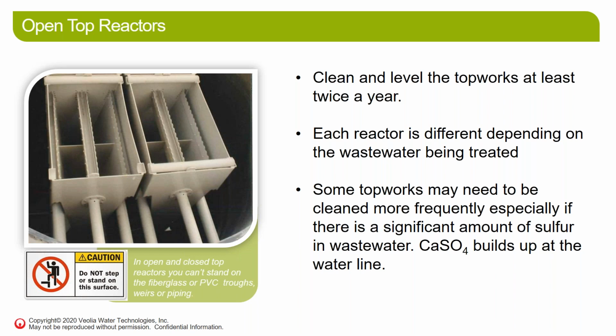So, yeah, in spots where we have more sulfur in the wastewater, calcium, you can get buildup of solids up at the top because in an open top reactor, you have anaerobic effluent with air. So you start producing some solids that kind of plate out or build up in that space where there's air and anaerobic effluent. So a lot of times if you have high sulfate concentrations in your wastewater, that converts to H2S, and if you take your covers off, you'll see this kind of white and yellowish crust and solids building up underneath your covers, and that's pretty much the sulfur coming out.